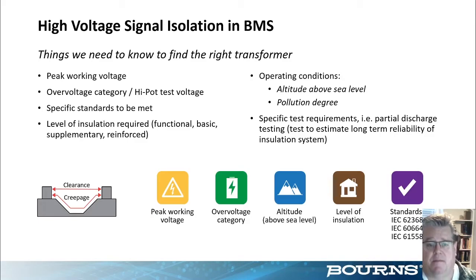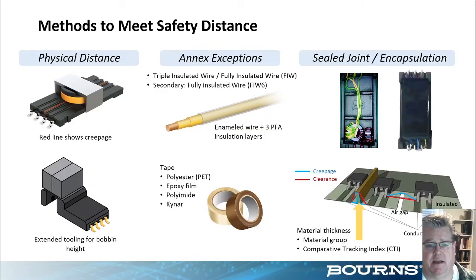There may be other operating conditions required for the transformer: does it need to operate above sea level? What is the pollution degree — the dirtiness of the environment? And are there any specific test requirements for reliability or longevity, such as life testing? All of these are collected in the process of designing a transformer.